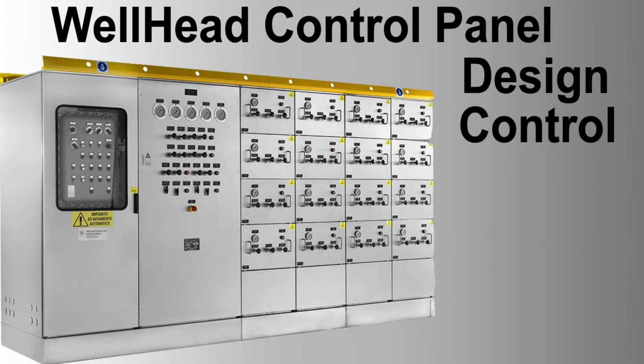4. Flow monitoring and stabilization. Once the SCSSV and SSV are open, allow the well to flow and stabilize. Monitor flow rate, pressure, and temperature parameters through the control system. Adjust choke settings if necessary to control the flow rate. 5. Steady-state operation. Ensure all control loops are functioning correctly and maintaining desired set points. Continuously monitor operational parameters and adjust as needed.